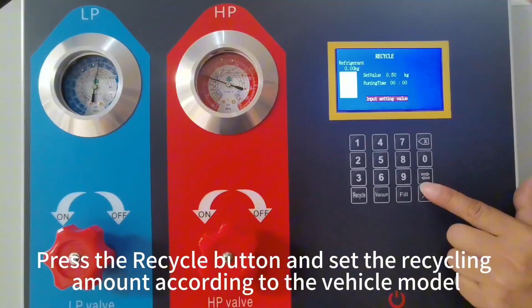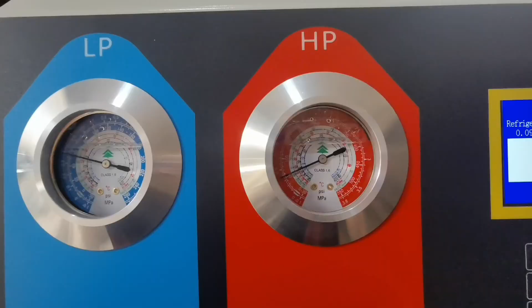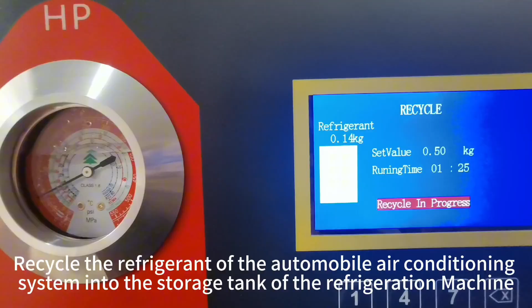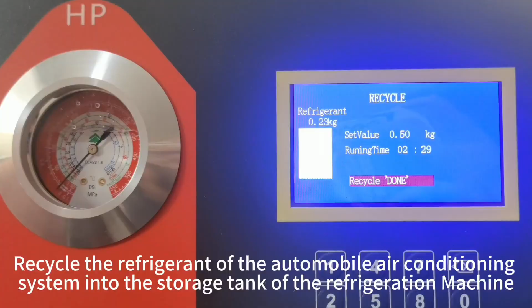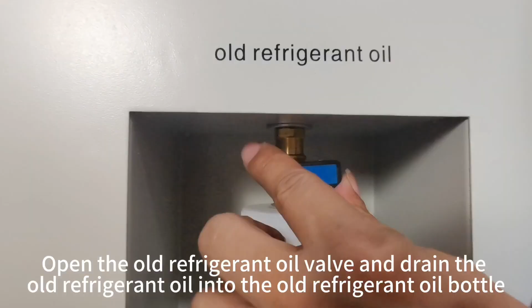Press the recycle button and set the recycling amount according to the vehicle model. Recycle the refrigerant of the automobile air conditioning system into the storage tank of the refrigeration machine. Recycle old refrigerant oil. After completing the refrigerant recovery, open the old refrigerant oil valve and drain the old refrigerant oil into the old refrigerant oil bottle. After completion, close the refrigeration oil valve.